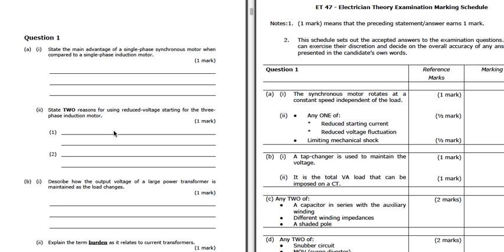Two reasons for using the reduced voltage starting for three-phase induction motors. So we don't want to put the induction motor straight onto a high voltage. So we reduce the voltage on starting, and that will reduce the starting current and reduce voltage fluctuation. It'll also limit the mechanical shock.